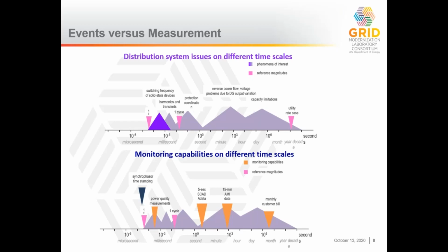Some of the other ones are looking at harmonics and transients in the system. Doing harmonic analysis is not that fun actually, but it requires a level of data, a level of accuracy, and a very specialized sensor to do correctly. You can make a mistake in doing a harmonic analysis of a system that can also cost tens of thousands of dollars if you don't have the right data to validate it. So just explaining the benefits of different types of phenomena and timescales and the issues they have there.